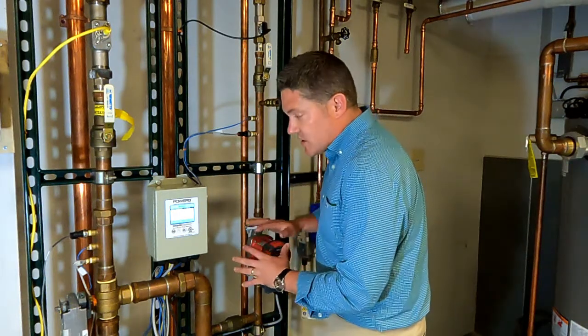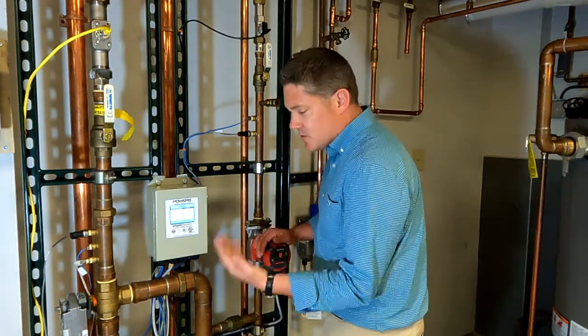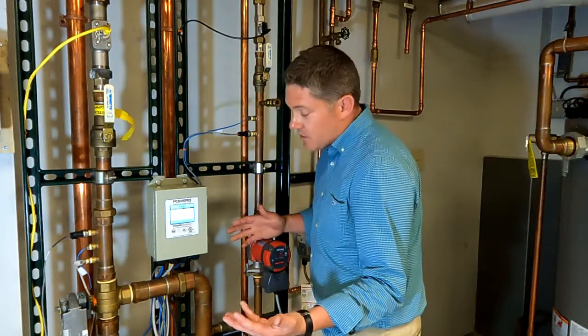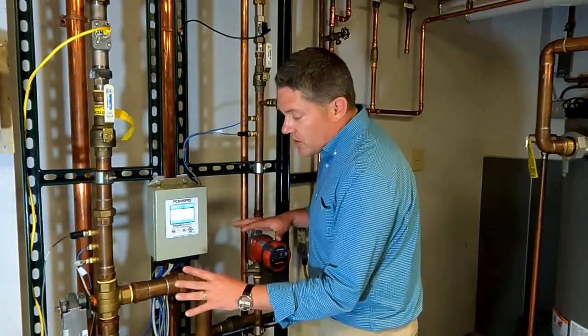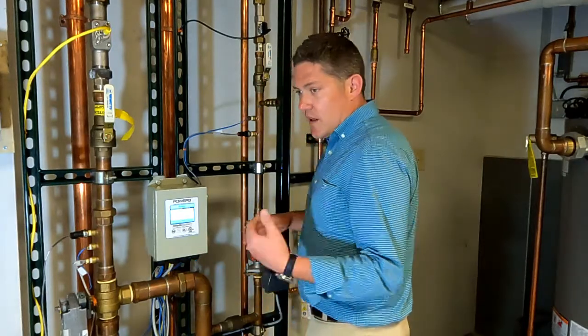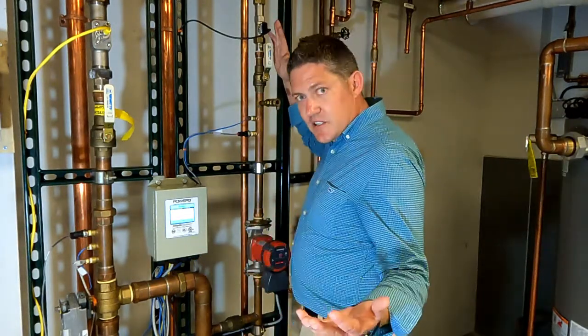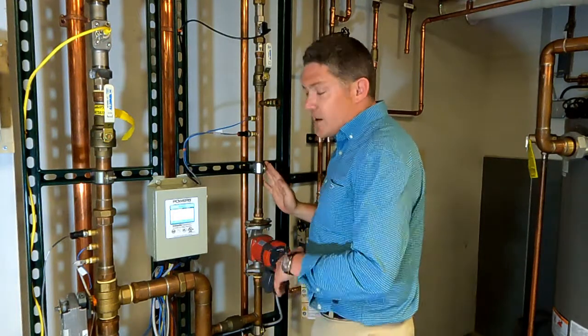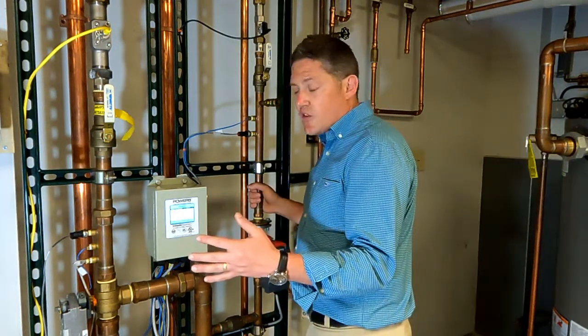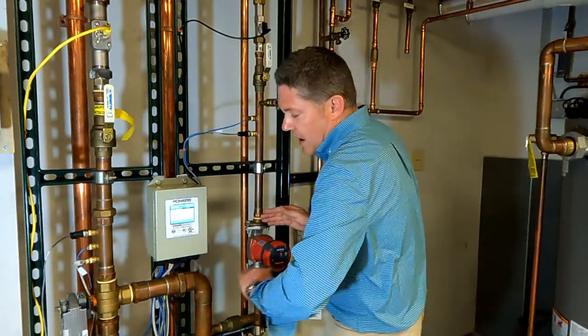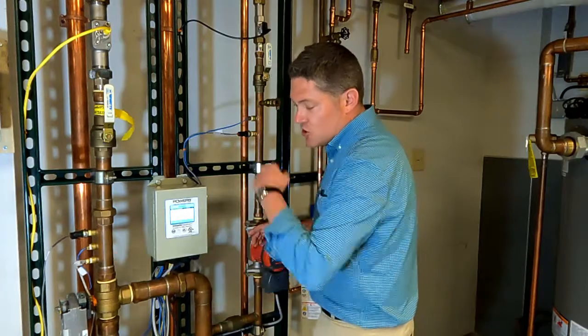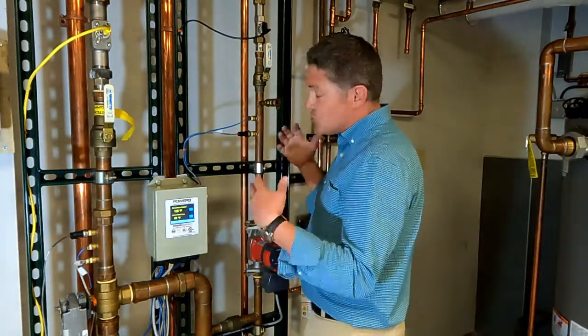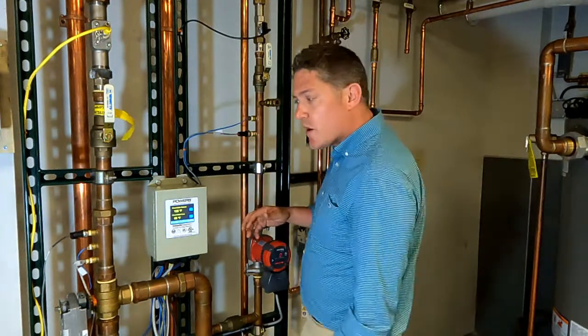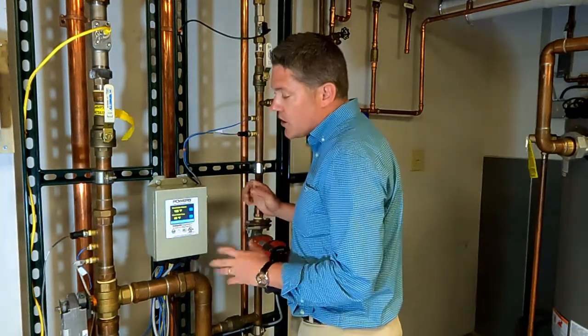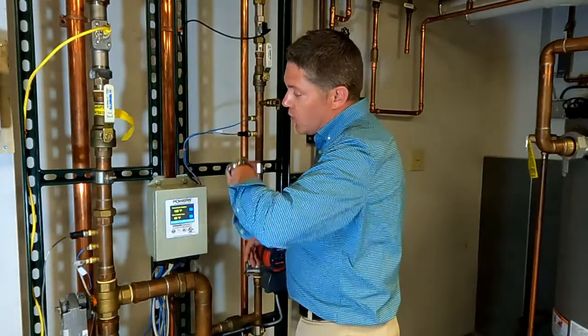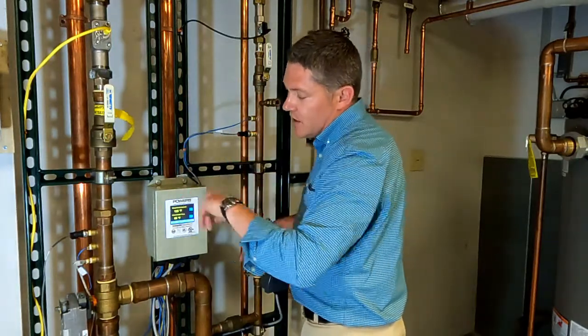In my opinion, I would just keep this on auto on. Just turning your pump on and off usually shortens the life of the pump. And this thing is self-balanced. Typically, like we talked about earlier, on a thermostatic setup, when your return water comes back, if you've got a closed loop system, meaning there's no draw on the system, and all the return water went back to the cold inlet, because there's no new water being introduced to the system, the pipes are completely full of water, there's no way to bring in new cold water from the street.